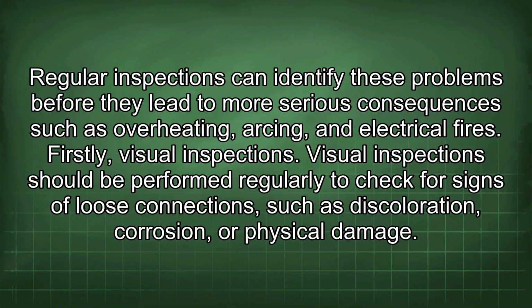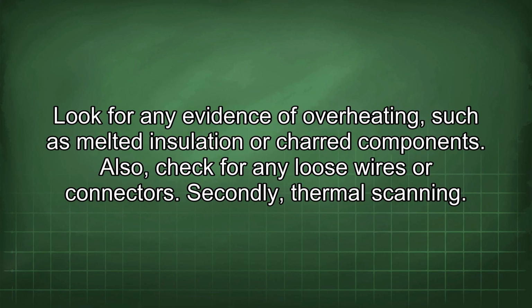Firstly, visual inspections. Visual inspections should be performed regularly to check for signs of loose connections, such as discoloration, corrosion, or physical damage. Look for any evidence of overheating, such as melted insulation or charred components. Also, check for any loose wires or connectors.